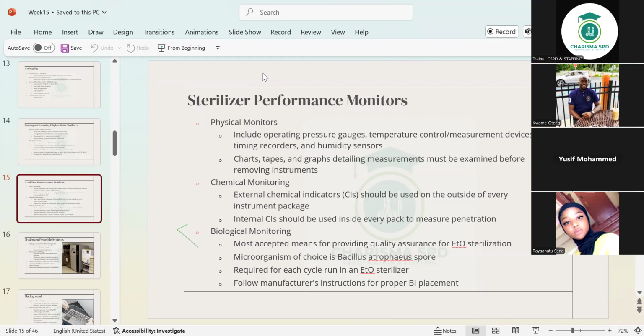The charts, tapes, and graphs detailing measurements must be examined before removing the instrument. And the tapes were what I told you about yesterday, when we saw an image with tape on the instrument. Before it goes in the autoclave, it could be gray and blue. Then when it comes out, the gray spot will be black, meaning it's good, it's sterilized. That's one of the physical monitors. And some are graphs detailing the measurements on the screen. You have to examine all those.